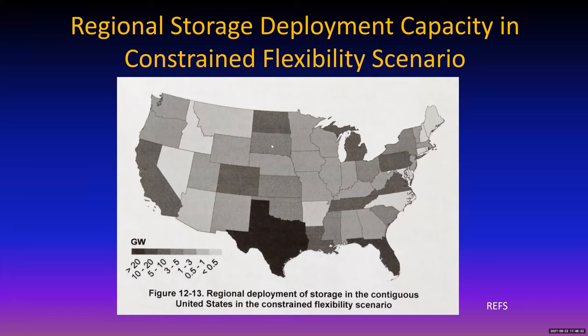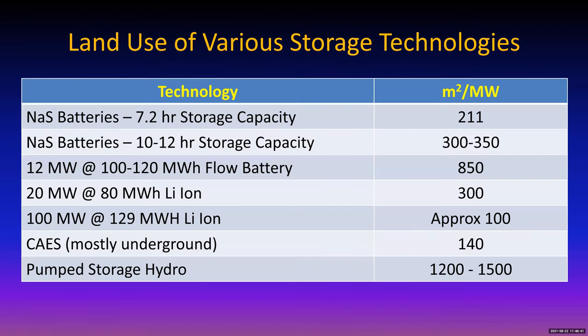So this is where educated guesses are being made as to where the storage is going to go. And here's how much space it takes for the storage. Sodium sulfur batteries with 7.2 hours of capacity - in other words, their full capacity can be depleted in 7.2 hours - it's about 211 square meters per megawatt.